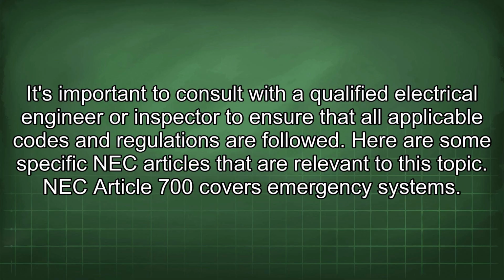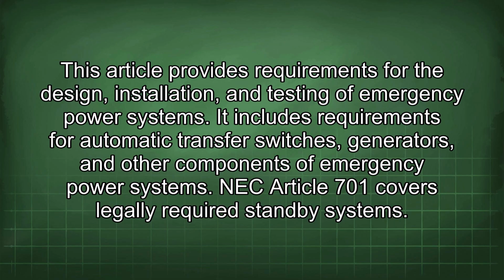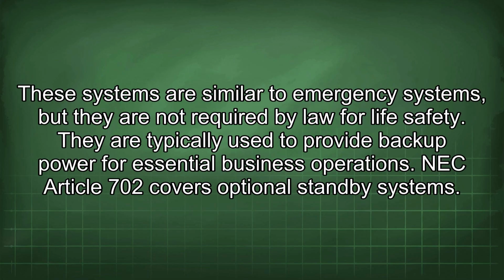NEC Article 700 covers emergency systems. This article provides requirements for the design, installation, and testing of emergency power systems. It includes requirements for automatic transfer switches, generators, and other components of emergency power systems. NEC Article 701 covers legally required standby systems. These systems are similar to emergency systems, but they are not required by law for life safety. They are typically used to provide backup power for essential business operations. NEC Article 702 covers optional standby systems.